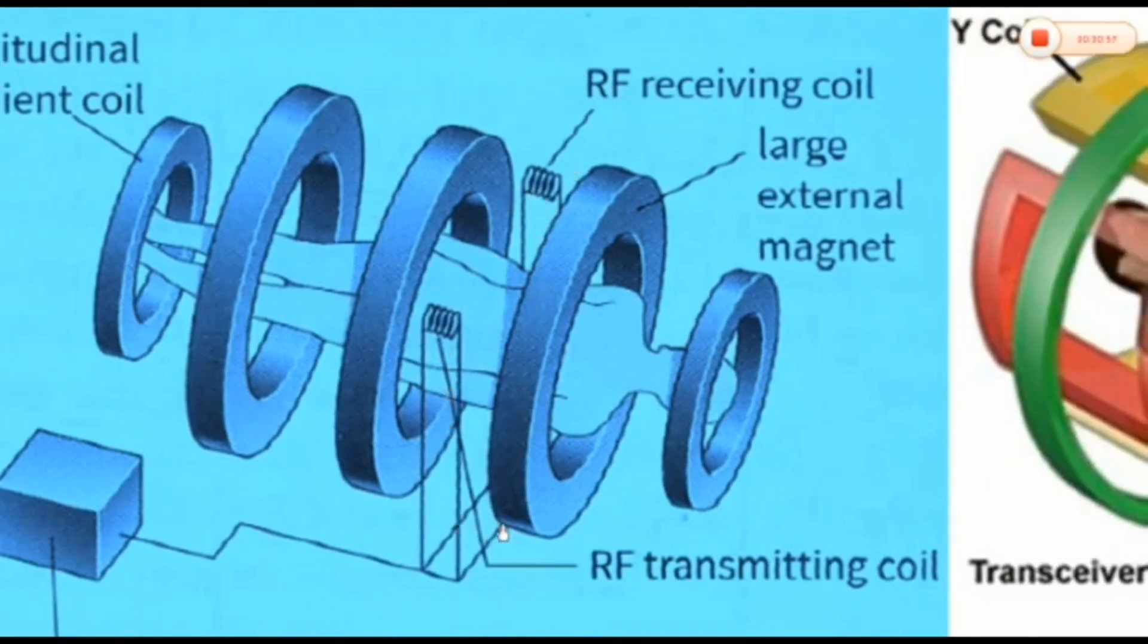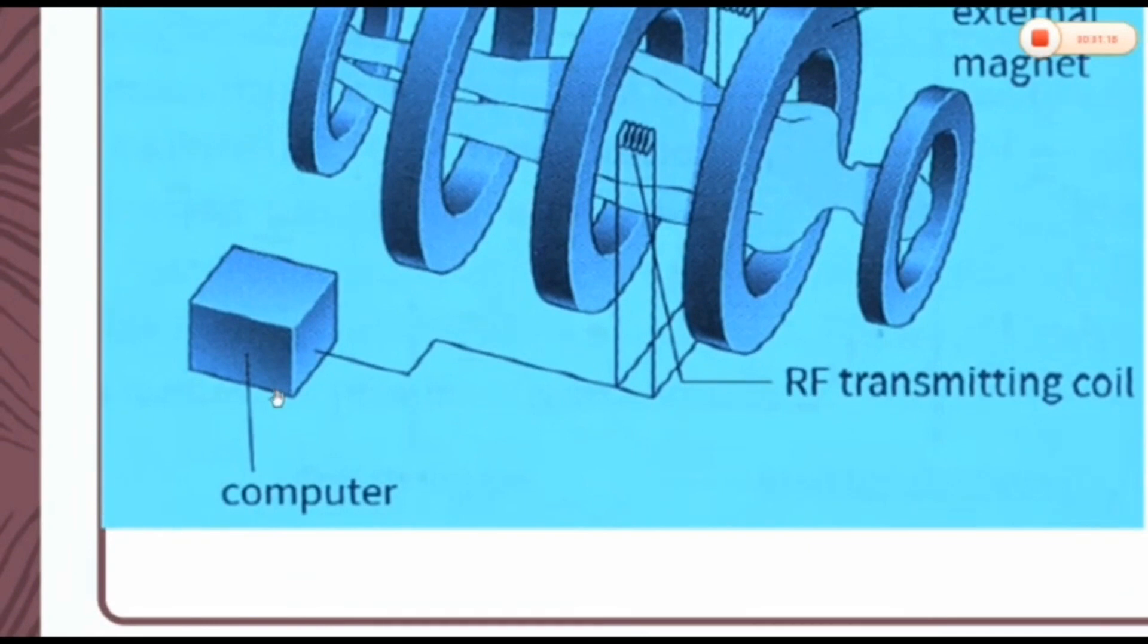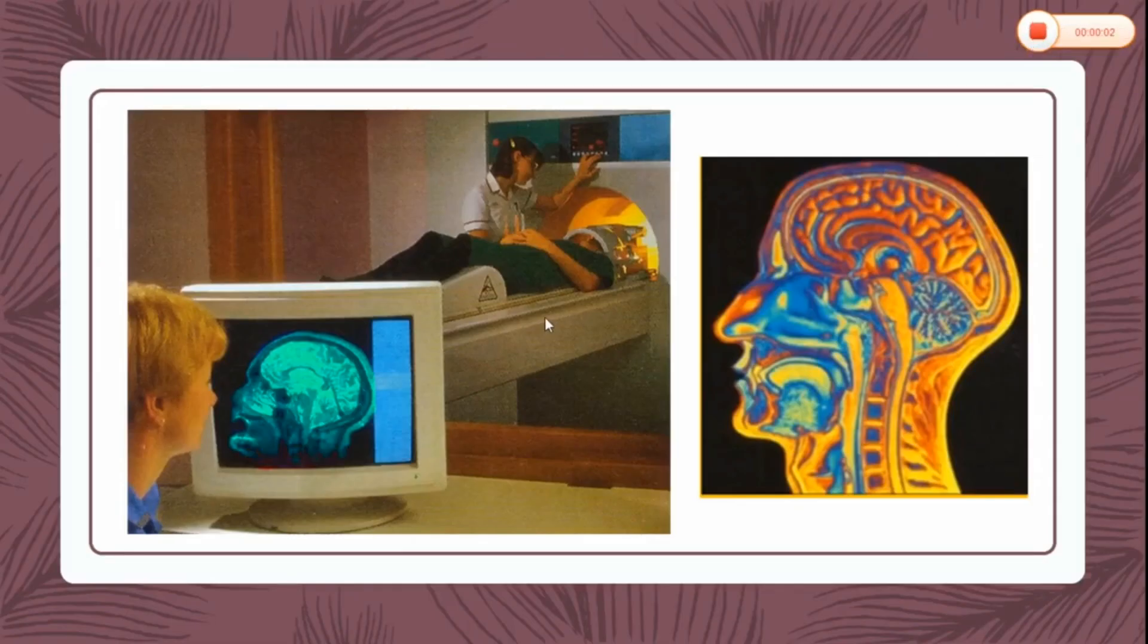These are the RF receiving and RF transmitting coils. Note that these RF signals are non-ionizing radiations. The RF transmitting coil transmits RF pulses into the body. The RF receiving coil detects the signal emitted by the relaxing protons. The computer controls the gradient coils and RF pulses, stores and analyzes the received data, and produces and displays images. In our next lesson, we will study procedure and working of an MRI scanner, and later we will also study its advantages and disadvantages and compare a CT scan with an MRI scan.